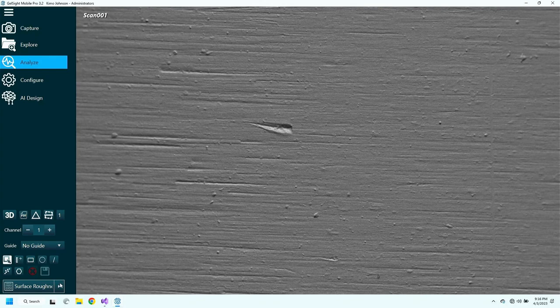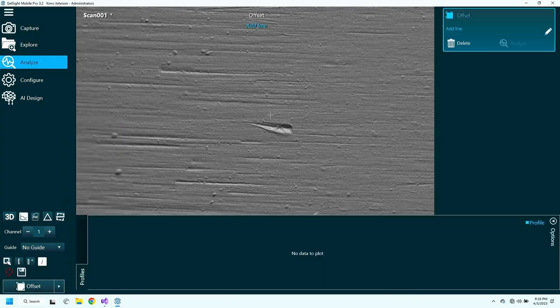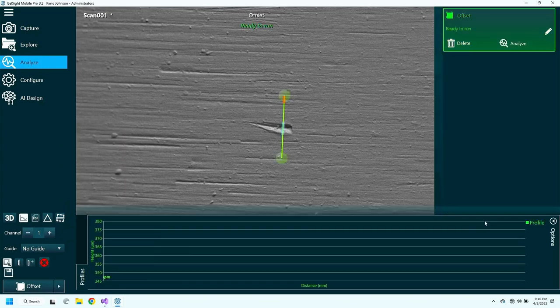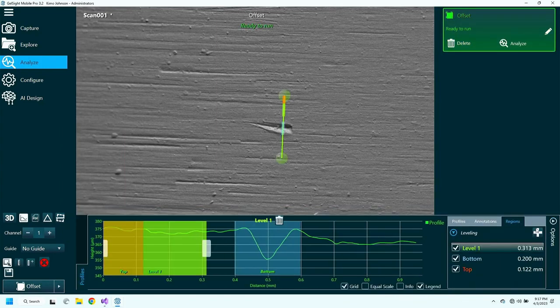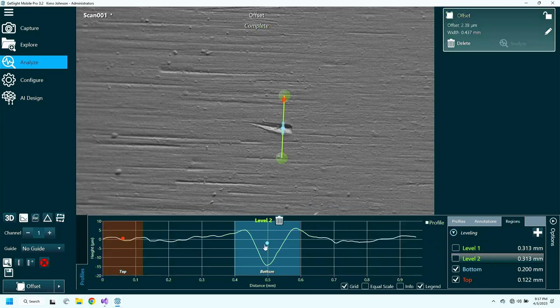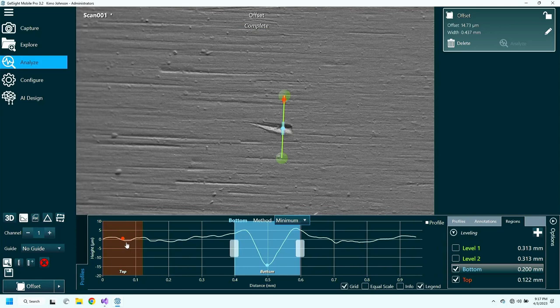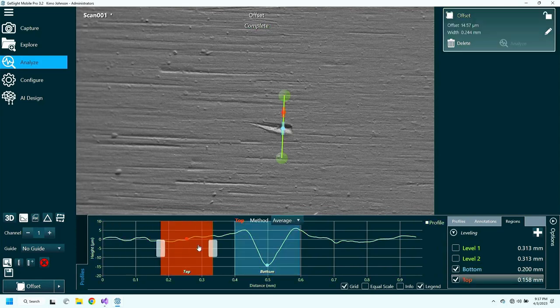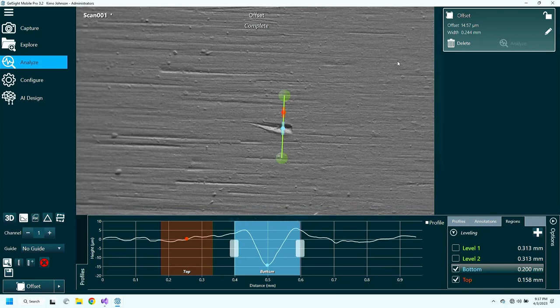The first thing I'm going to show is how we can measure the depth of a small scratch on the surface of this part. I'll choose the offset tool and drag a line across it. We can then level the surface and set the max and min points. The red is used to set the max, and I'm telling it to average the height of the surface in that region. The blue is set to find the minimum, and here it says that that scratch is approximately 14.6 microns deep.